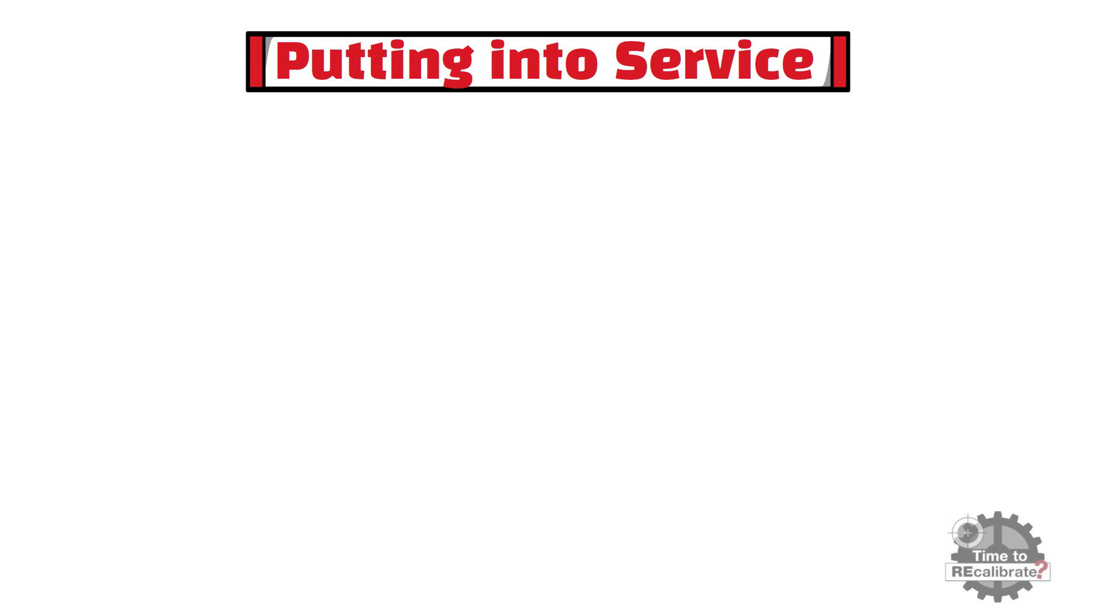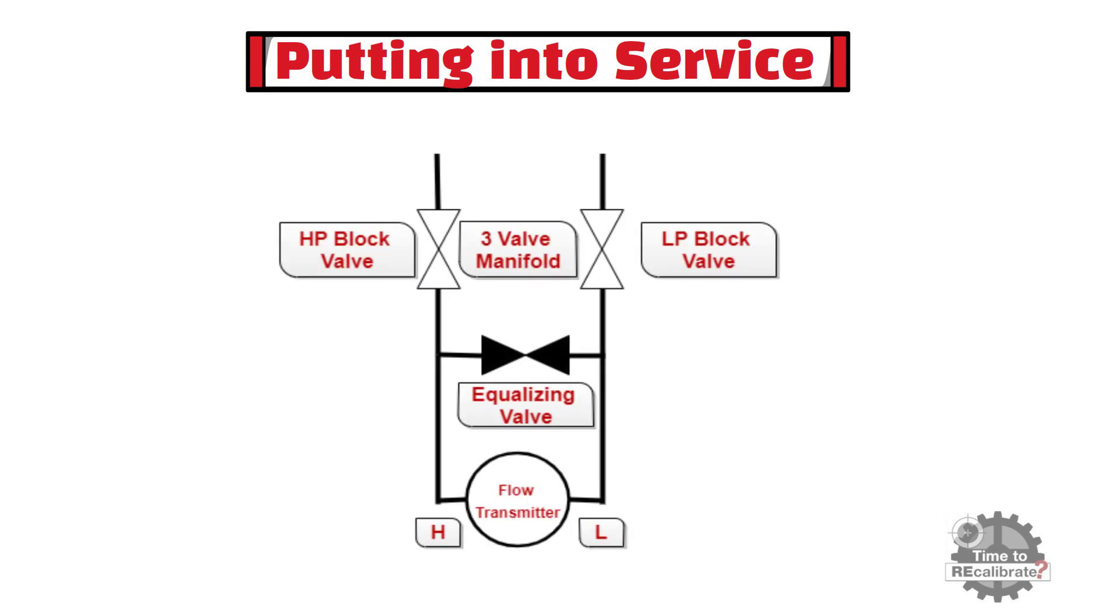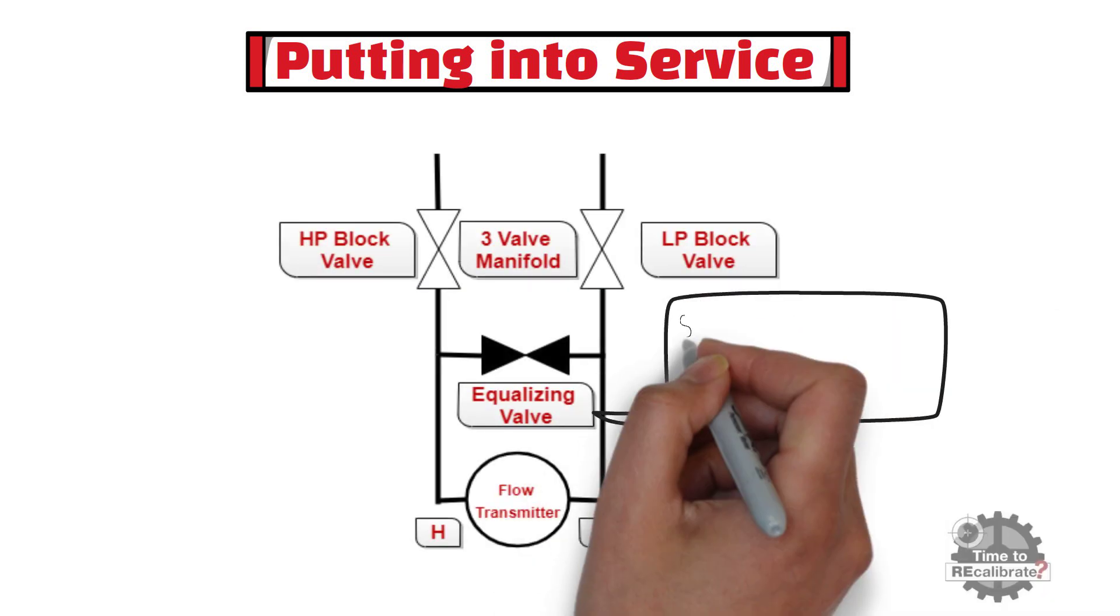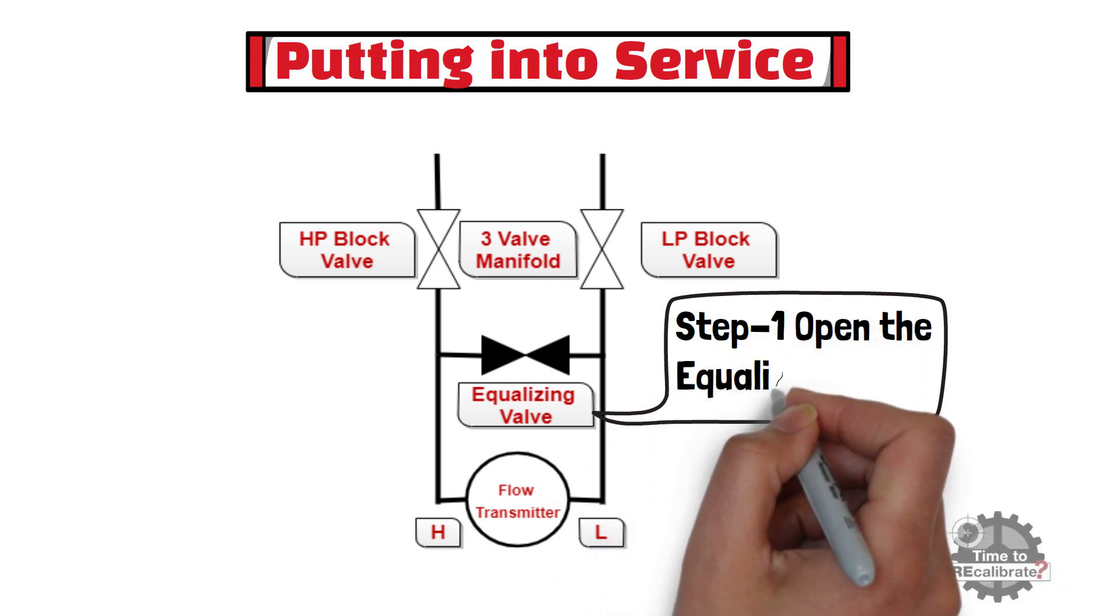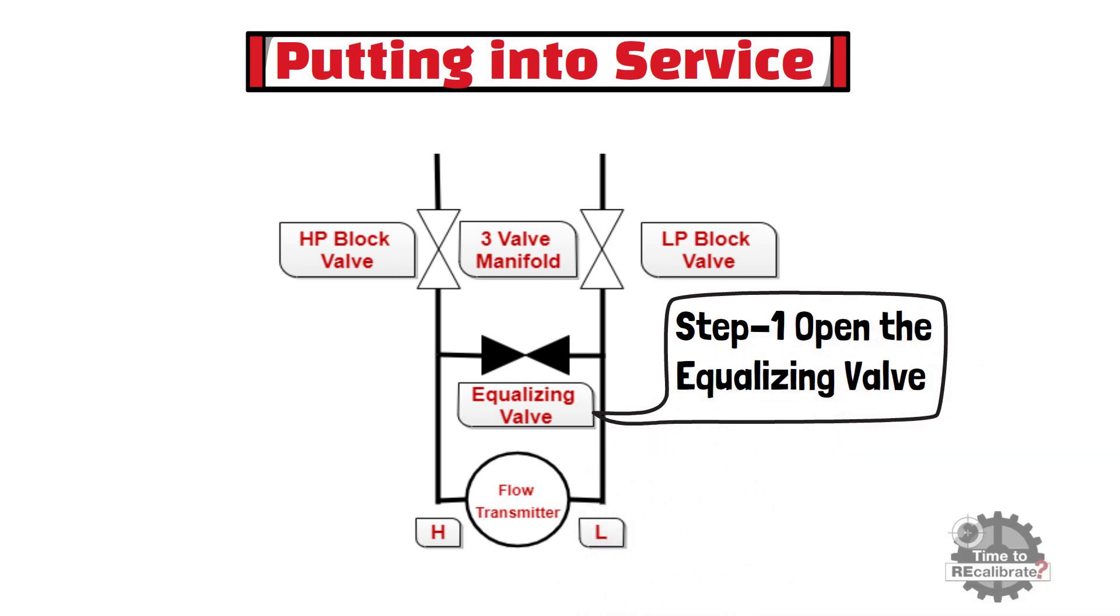Now, let's learn how to put transmitter back into service. In step 1, first of all, open the equalizing valve by rotating valve in counterclockwise direction. This will balance the pressure between the high and low side, and prevent over-ranging during this process.